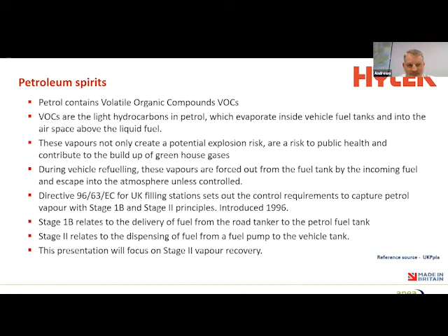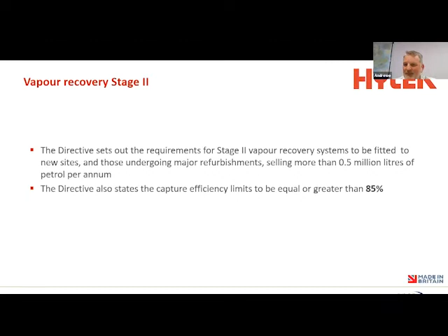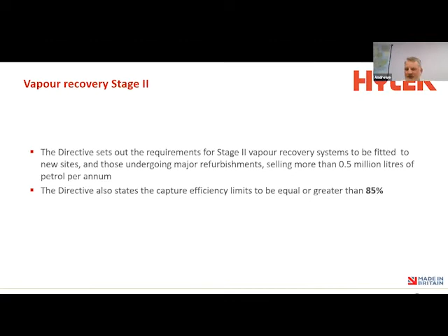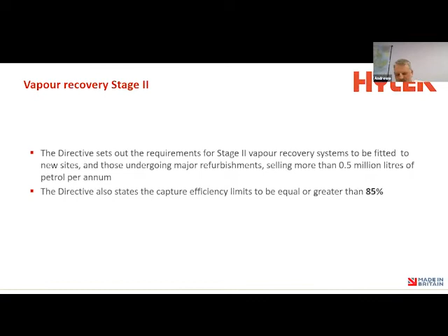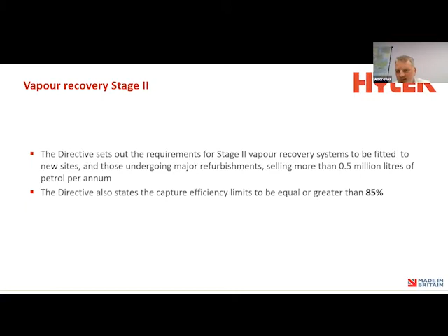Within the directive, it sets out the requirements that stage 2 vapor recovery should be fitted to new sites, those undergoing major refurbishments and selling more than 500,000 litres of petrol per annum. It also sets out that the capture efficiencies need to be greater than or equal to 85%. That means for every 100 litres of petrol we are dispensing, we are looking to capture 85 litres equivalent of vapour.